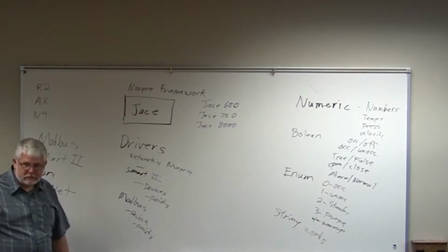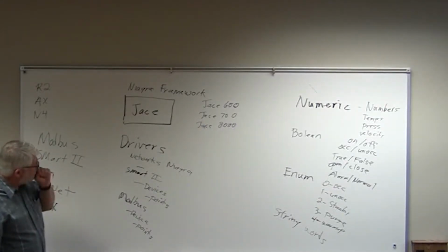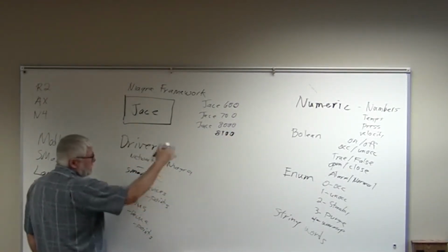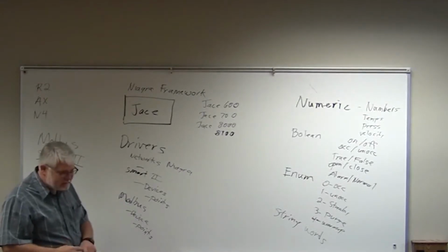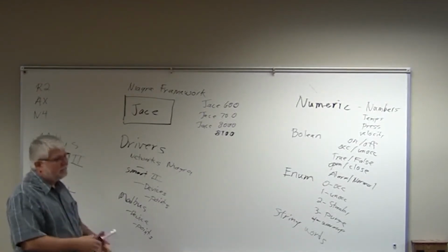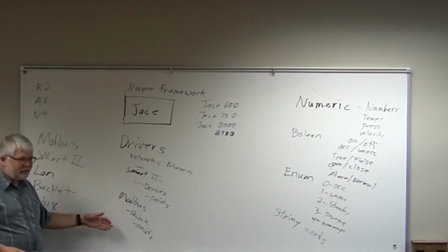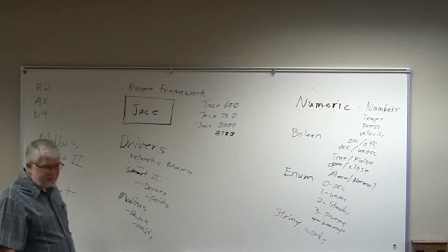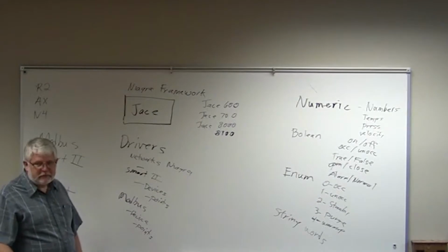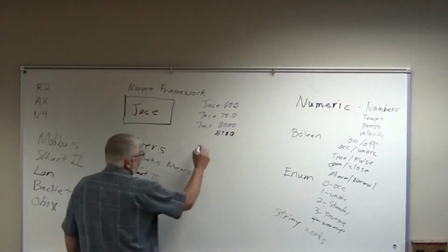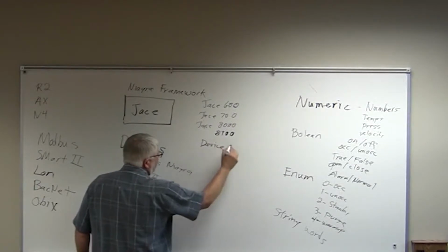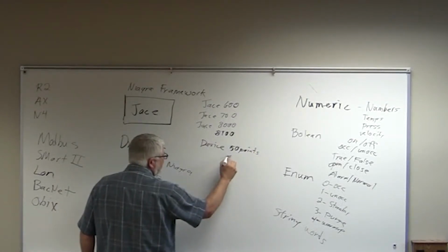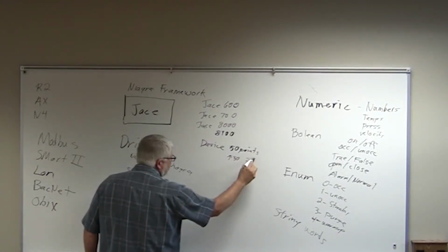Does that make sense? So if you bought a Jace 8100, it would mean it could handle 100 devices. And what's a device? A VAV, a VFD, a chiller. So are they limiting that based upon points? There's a next piece to that, right? Each device can have 50 points pulled in. If you go above 50, it's a second device.